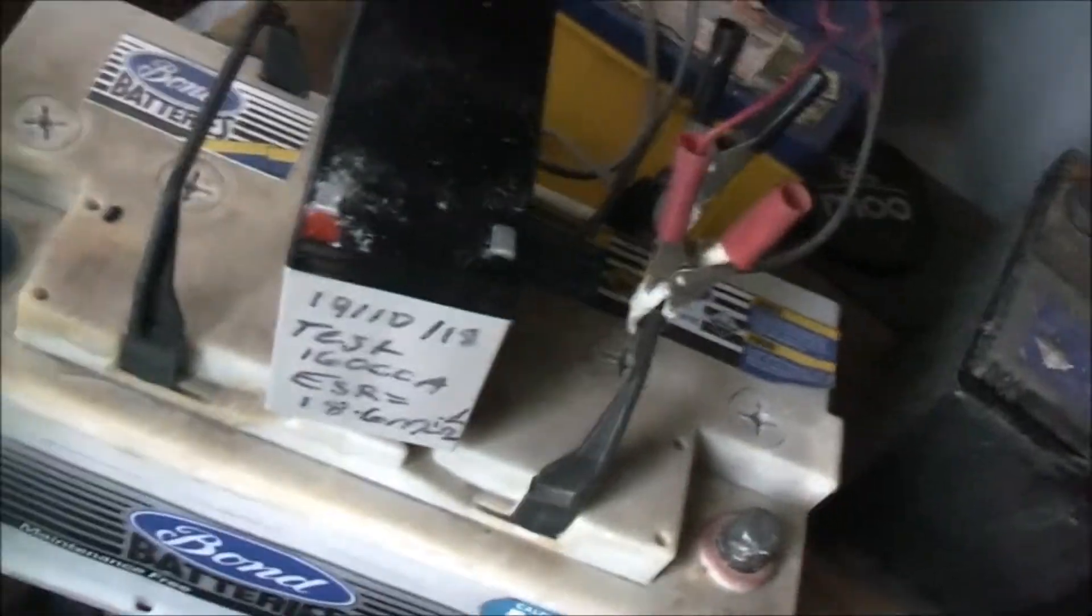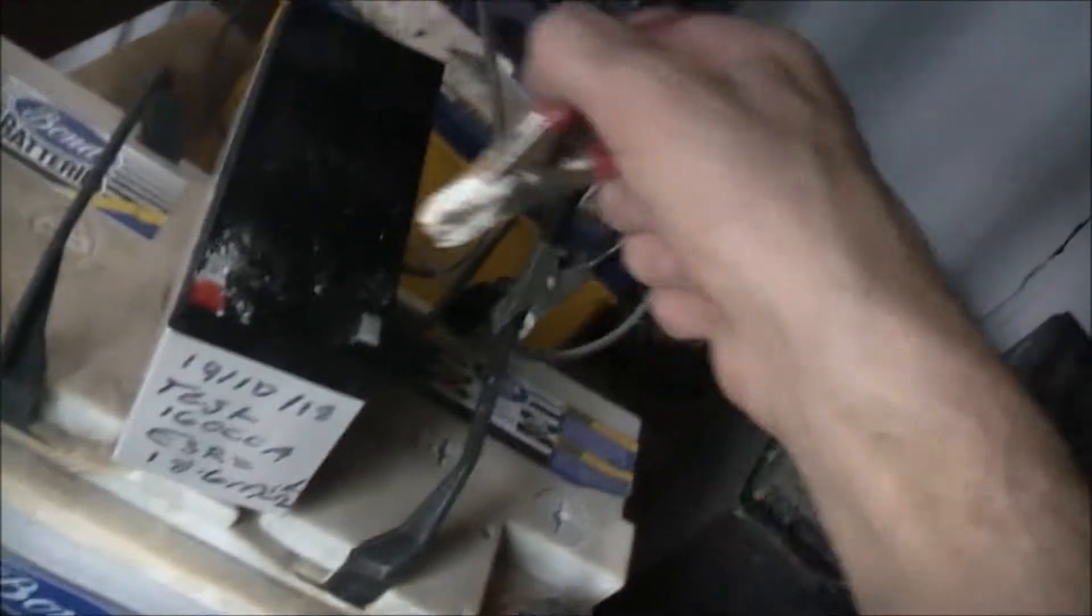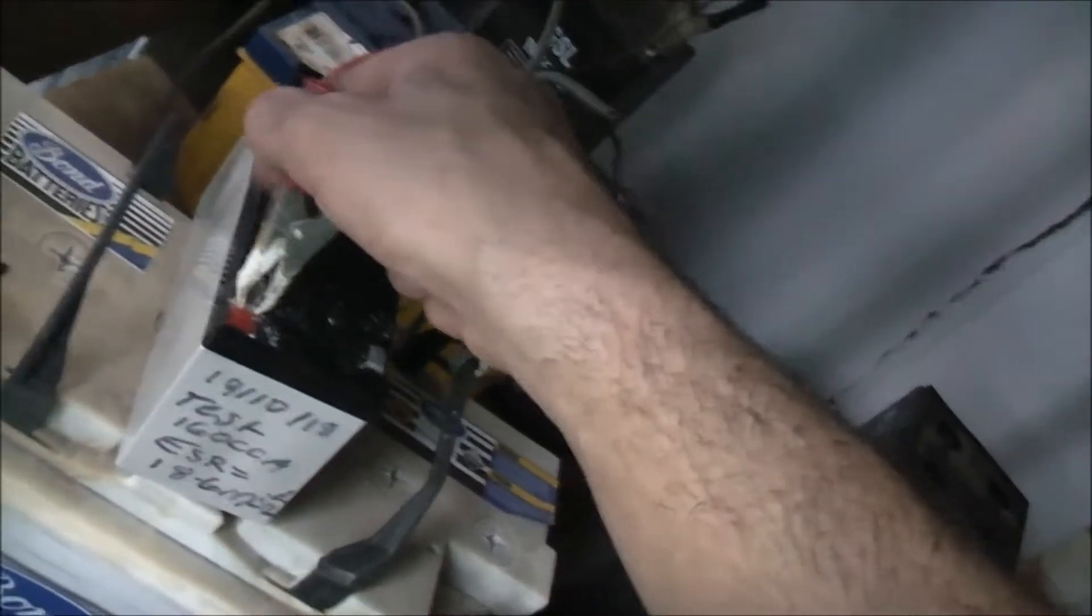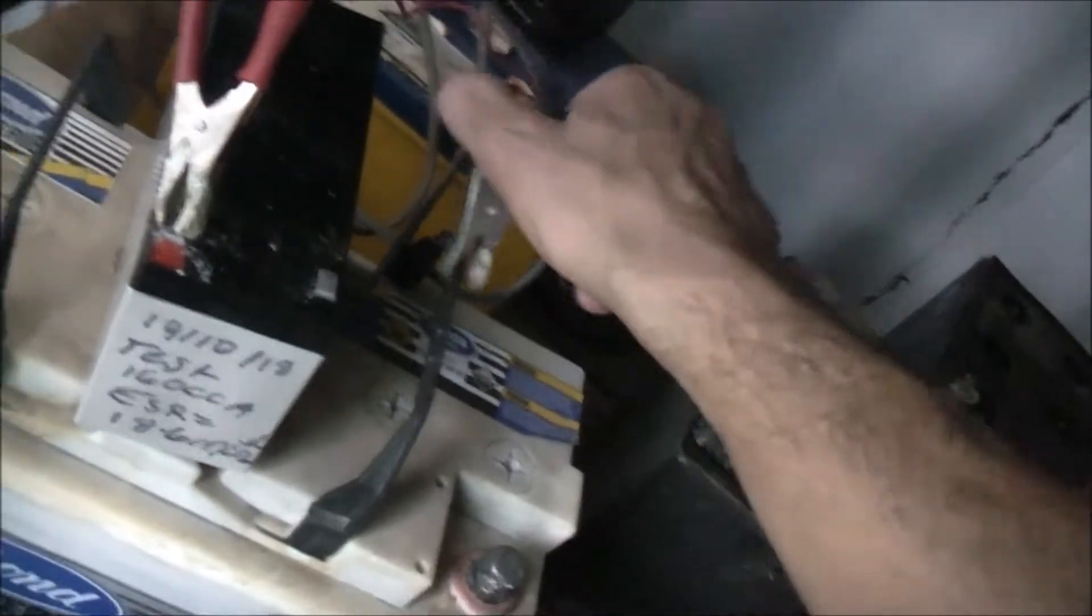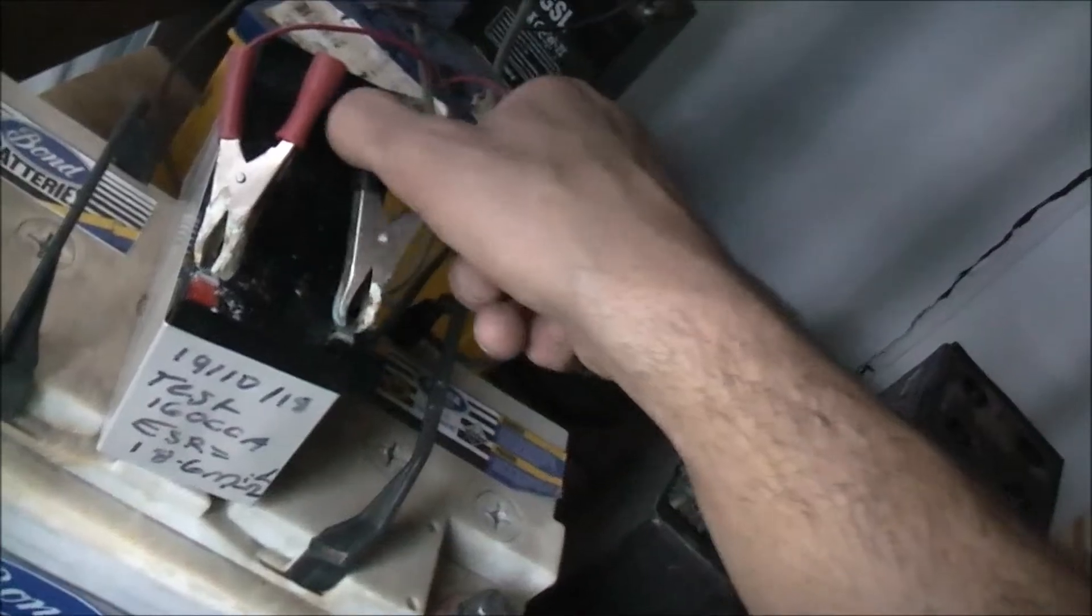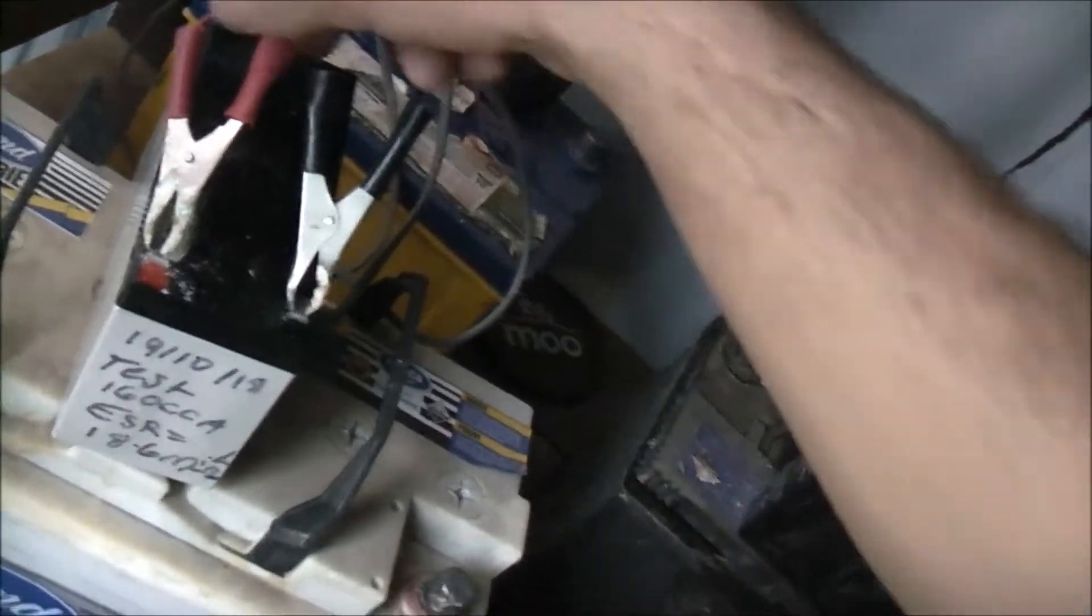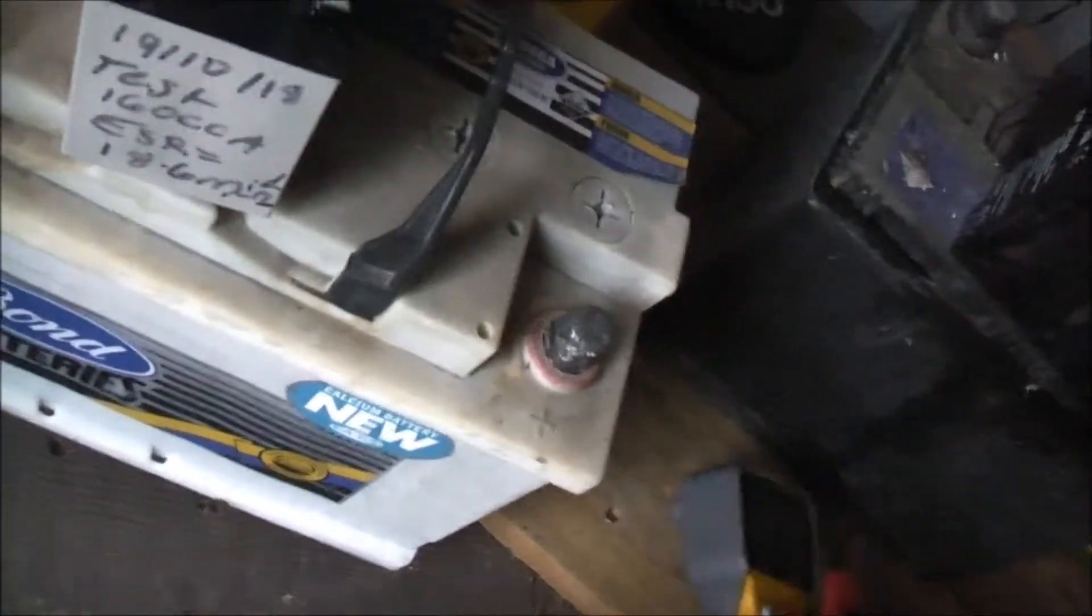She blew the anode plate set of this battery right out. She cooked the anodes. Usually when that happens, the battery is at the end of its service life. I mean, it is from 2007. That's a very old battery. They've done pretty well, though.